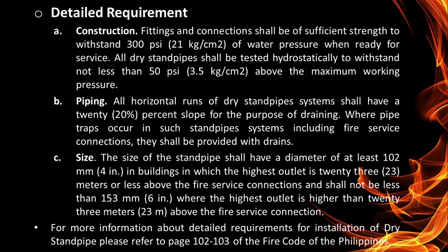Next is piping. All horizontal runs of dry standpipe system shall have a 20% slope for the purpose of draining. Where pipe traps occur in such standpipe systems, including fire service connections, they shall be provided with drains. Next is size. The standpipe shall have a diameter of at least 102 millimeters in buildings in which the highest outlet is 23 meters or less above the fire service connections, and shall not be less than 153 millimeters where the highest outlet is higher than 23 meters above the fire service connection. For more information about the detailed requirements for installation of dry standpipe, you can refer to the Fire Code of the Philippines, page 102 to 103.